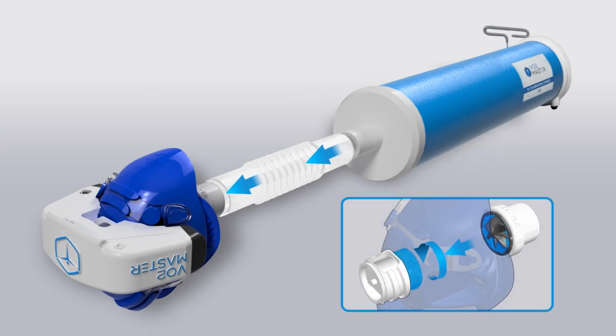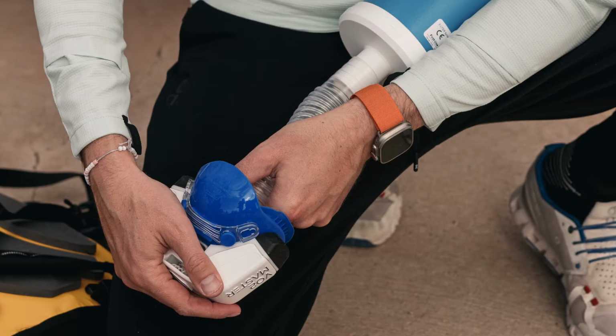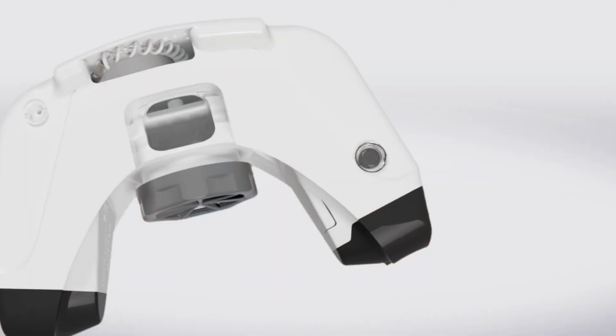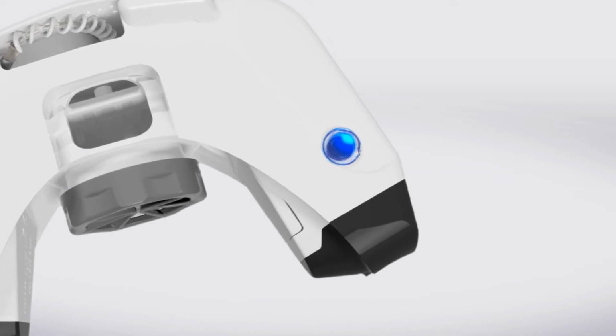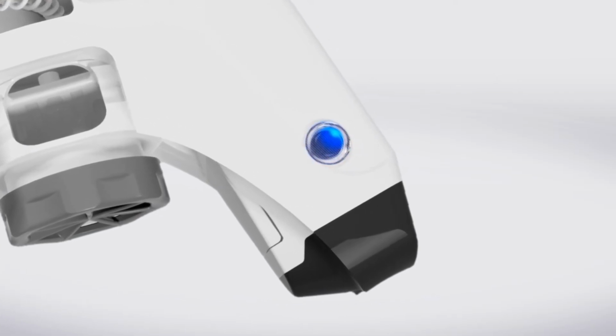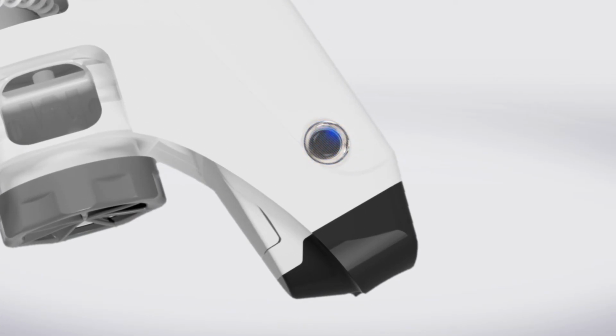Note that the analyzer is to be positioned with the breathing port facing up during calibration. Ensuring the analyzer is properly connected to the syringe, we will then power on the analyzer and allow it to remain undisturbed until the zero calibration process has been completed. This is identified by the pulsing indicator light changing from royal blue to cyan.